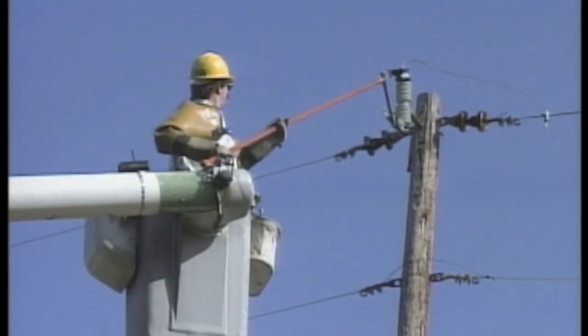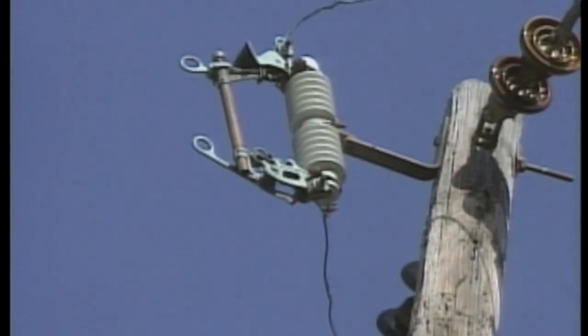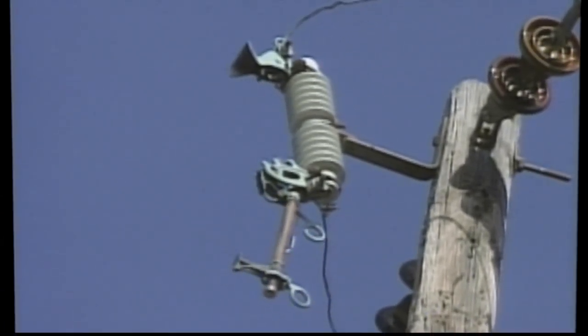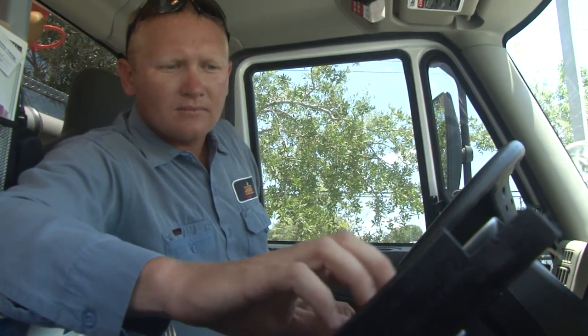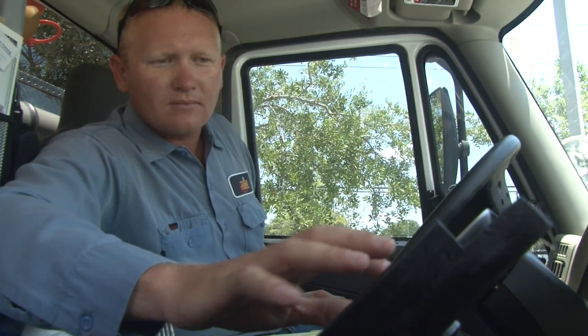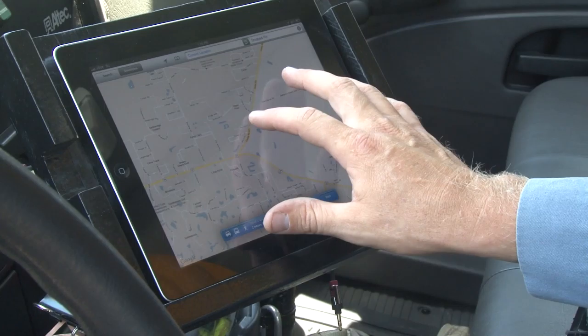One clue to this situation is that when the troubleshooter closed in the cutout, the primary fuse held for a few seconds, then burned open — it didn't blow. The troubleshooter remembers similar situations where primary fuses burned open because of cold load pickup, a situation which can occur when too large of a load is placed on the system too quickly.